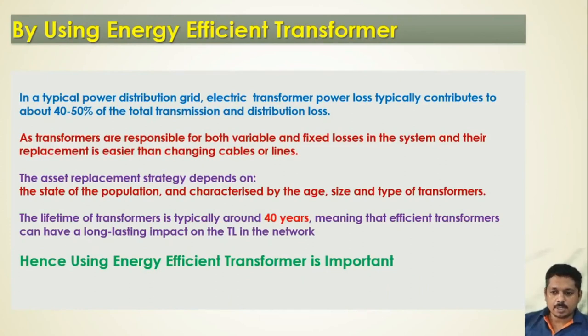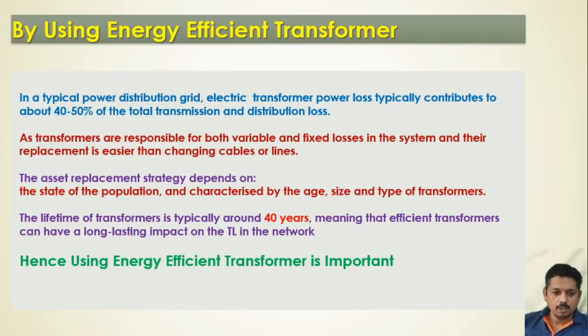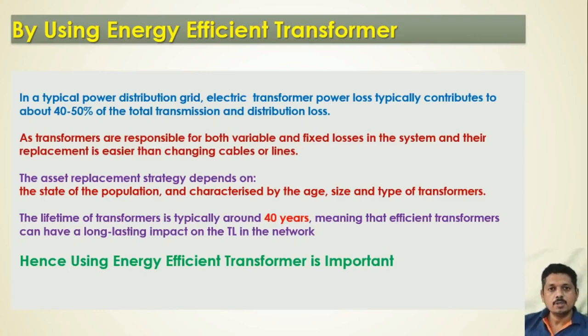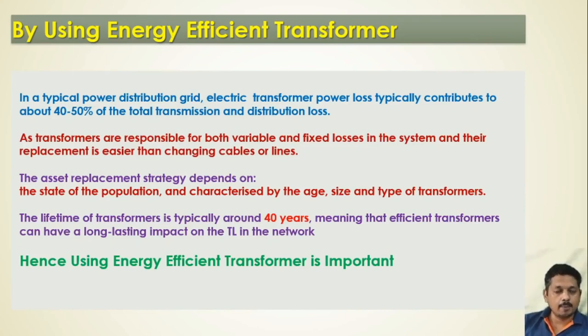Next is using energy-efficient transformers. In distribution networks, transformer power loss is around 40 to 50 percent of total transmission and distribution losses. It is therefore very important to address these losses. Transformers are responsible for both variable and fixed losses, and their replacement is easier than replacing cables or entire lines. The typical life of a transformer is around 40 years, so selecting an energy-efficient transformer is critical.